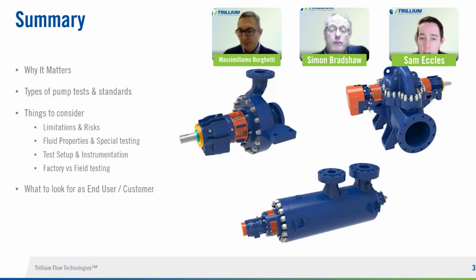During the hydro test, when the ambient temperature drops, what is the tolerance of pressure drop from a pump perspective, and is there any standard we can use? Okay. The standard to be used is API 610. What is written in the standard is that no pressure drop is allowed. The practical way is that some stabilization of the fluid is generally there, and some accuracy of the instrumentation has to be considered. But you have to be sure that the pressure drop is not due to any leak. And the other main recommendation is not to have a huge drop of temperature during the hydro test. This is the quick answer.